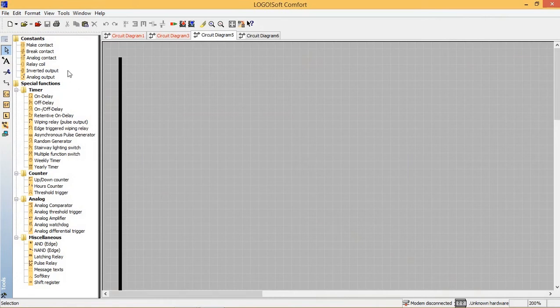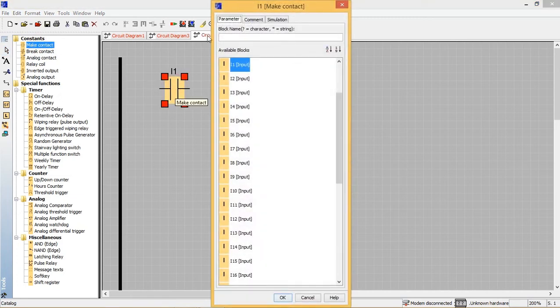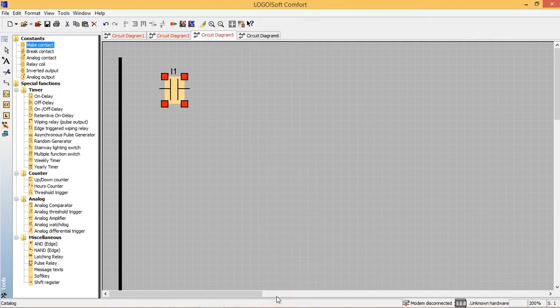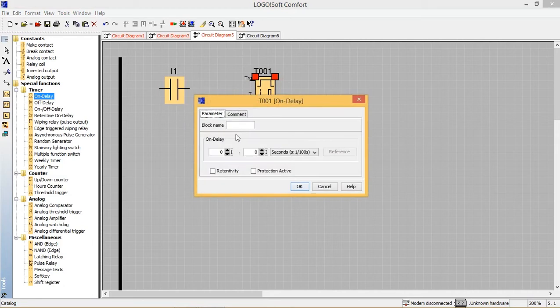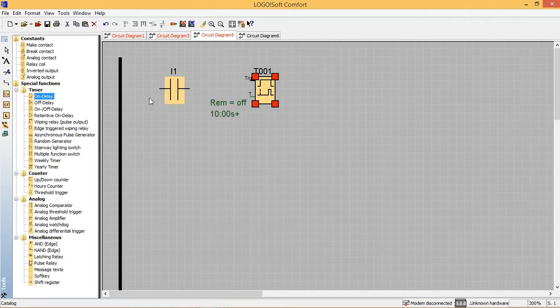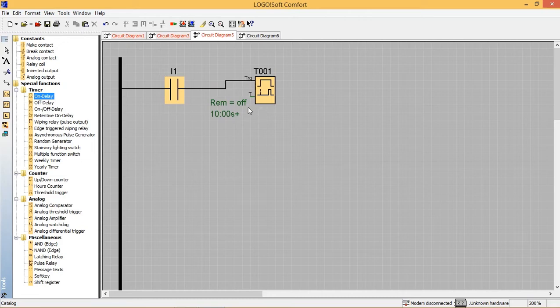Here I am using an ON-delay timer. This is your input I1. An ON-delay timer is taken and a time delay of 10 seconds is being set. As you know, an ON-delay timer means when you give input, after 10 seconds only the output coil will be energized.